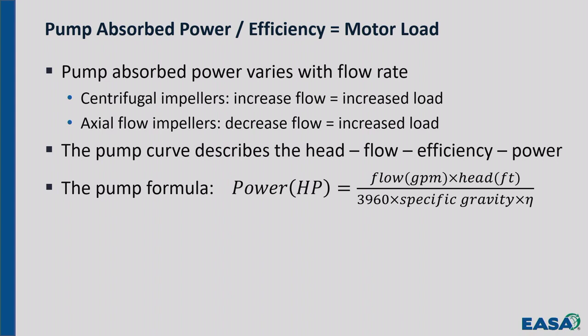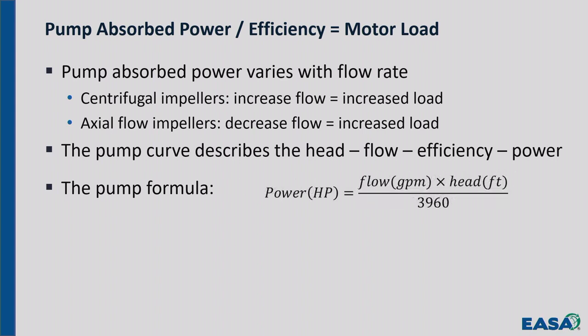The little character on the end, the Greek eta, stands for efficiency. That's what engineers use when they don't want to write out the word efficiency. They use a little character. Well, let's suppose our pump were 100% efficient. We can deal with the efficiency later. Let's just suppose our pump was 100% efficient, and it was pumping water. Then I don't have to worry about either one of those two, and my formula gets simpler. Flow times head divided by 3960 is power.